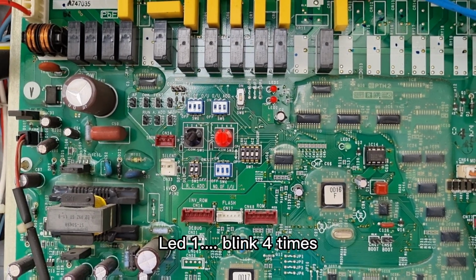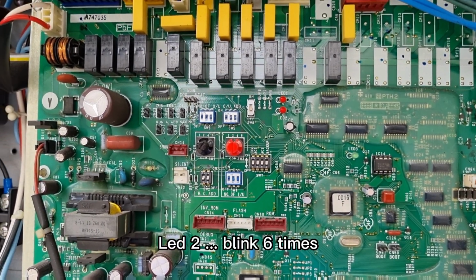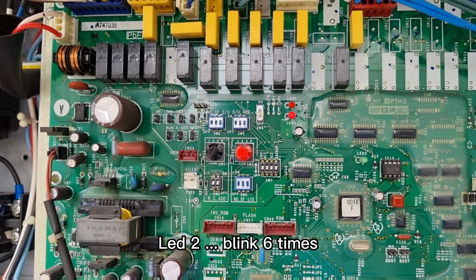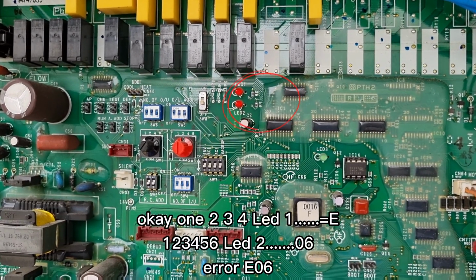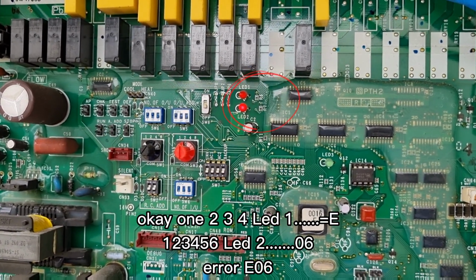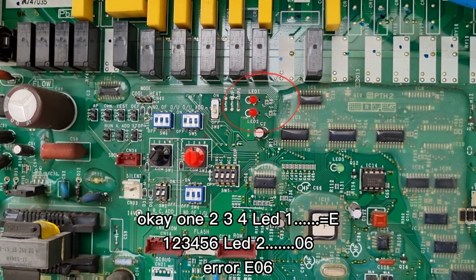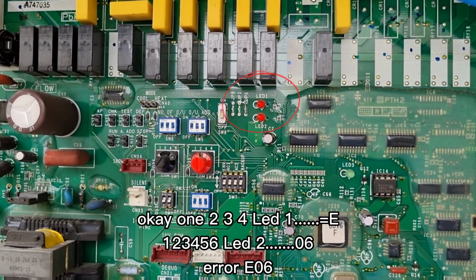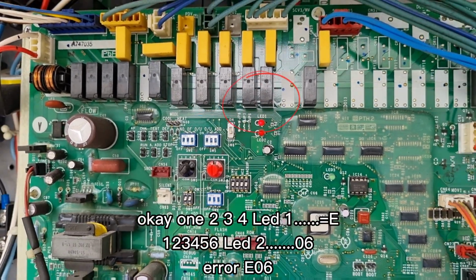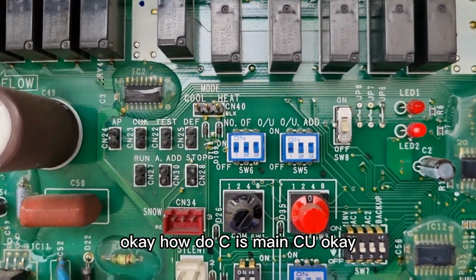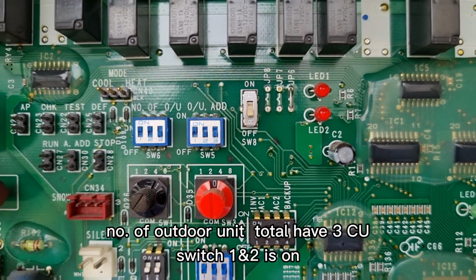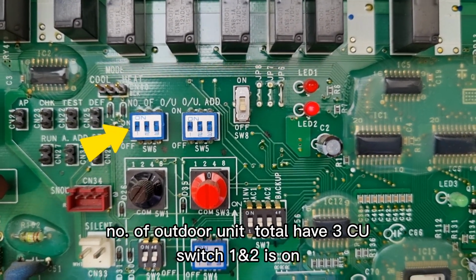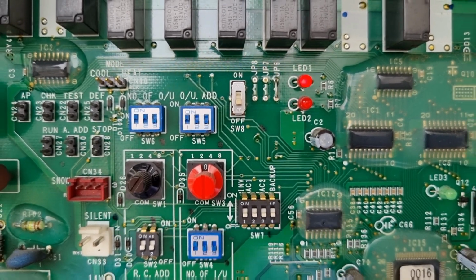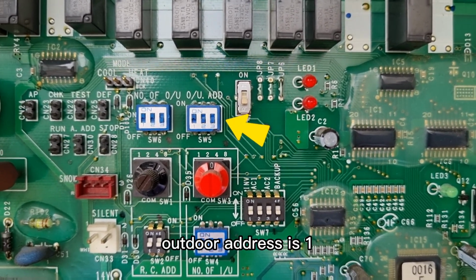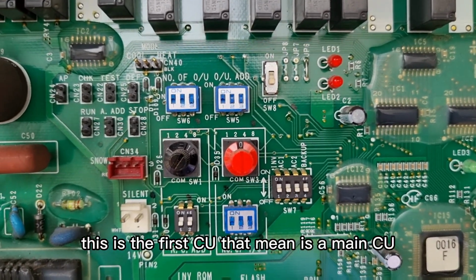LED 1 blinks 4 times. LED 2 blinks 6 times. Okay, 1 2 3 4. LED 1. 1 2 3 4 5 6, LED 2. The error is E6. Okay, how to see the main CU: the number of outdoor units, total 3 CU. 1 and 2 is on. Outdoor unit address is 1. Okay, this is the first CU. That means it's the main CU.